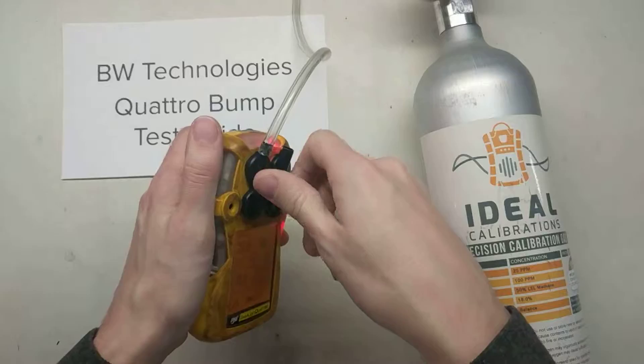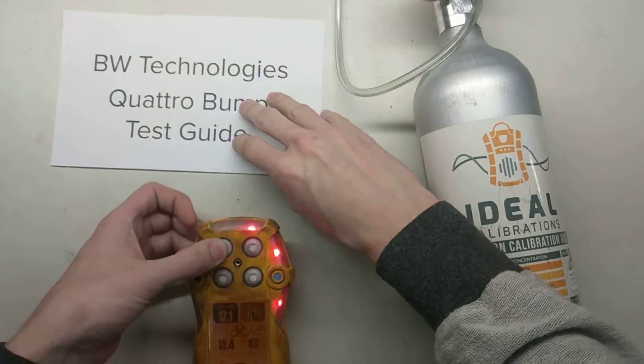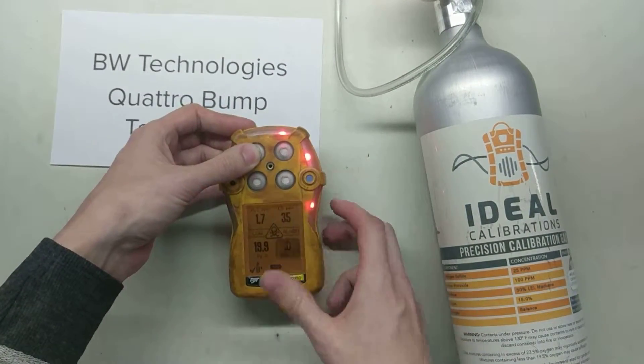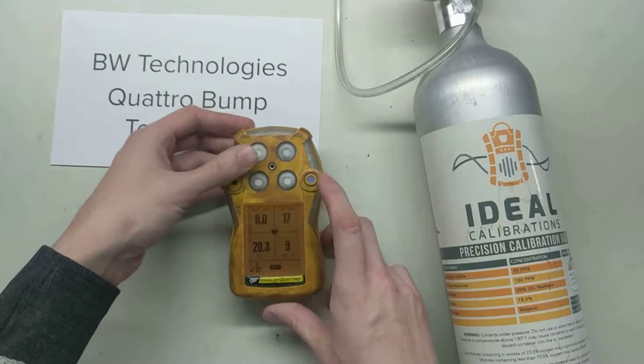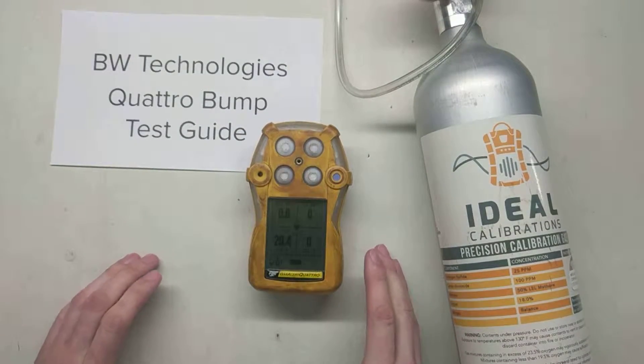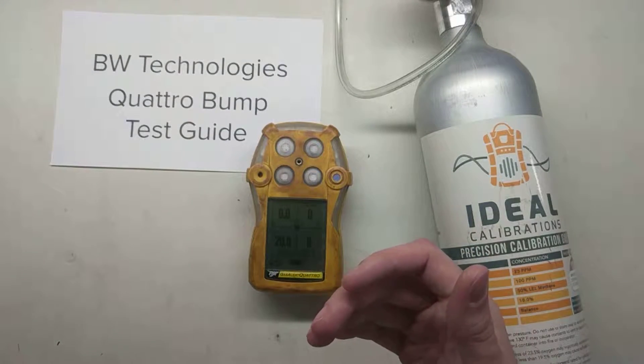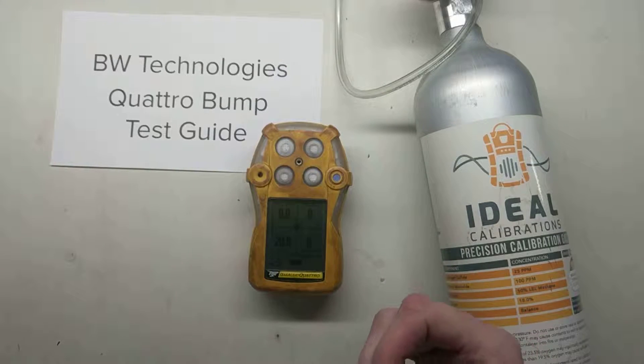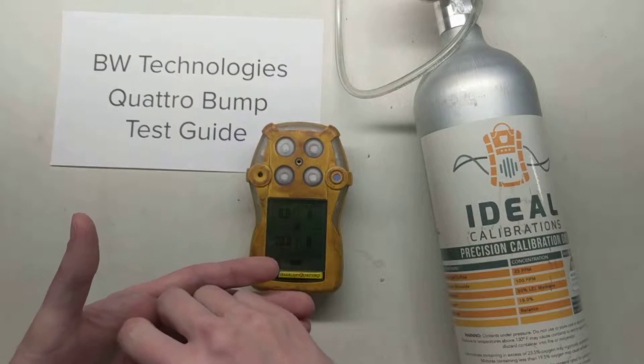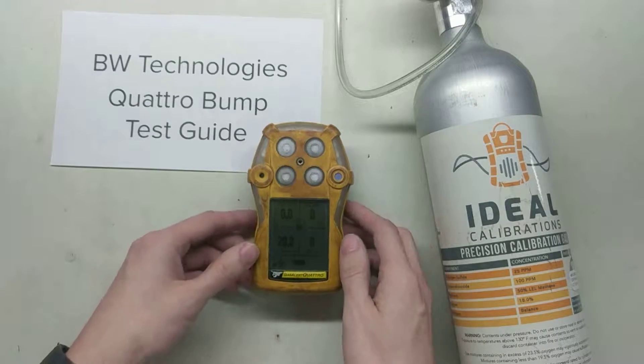Now take off your calibration adapter. I'll put my thumb over that so we can save our ears for a little while. Now the next thing to do that's very important: we want to make sure that we record that we've done this, because if anyone inspects, you've got a record. Grab a piece of paper — we have a spreadsheet available online in the description. All it needs is today's date, your initials, that the audible alarm passed, that the strobes passed, that the horn passed, and that the sensors were moving. And that's it — you're all said and done.